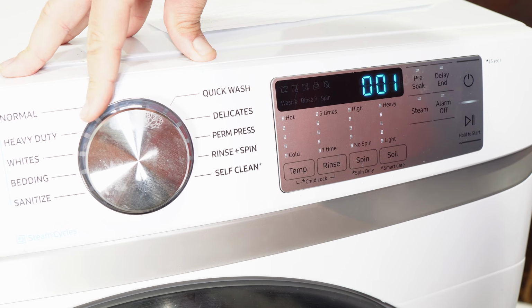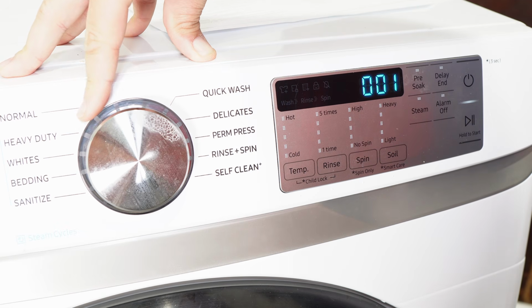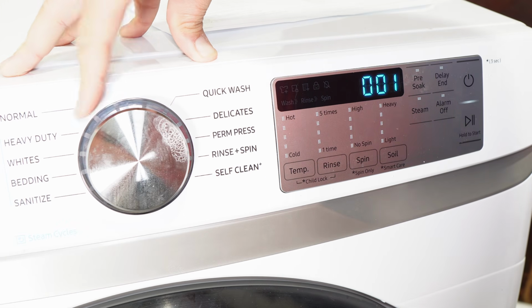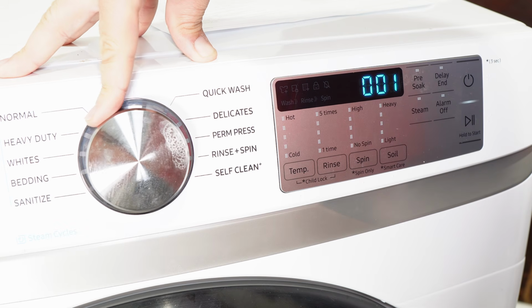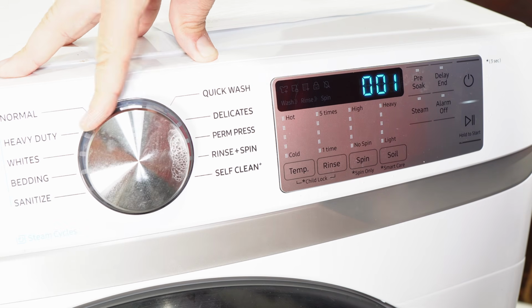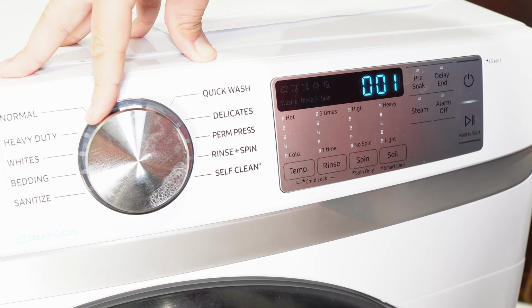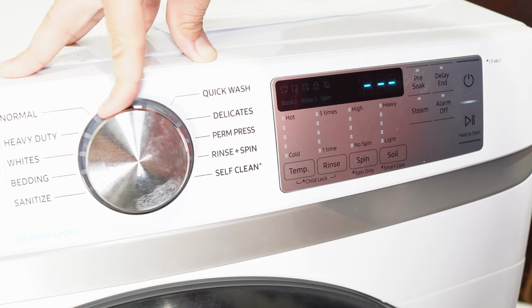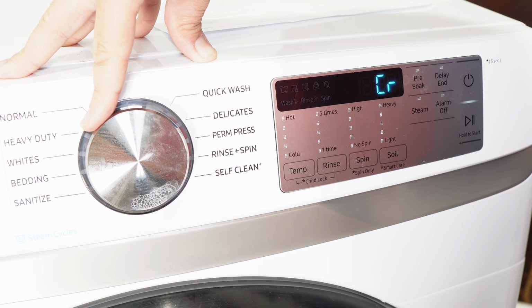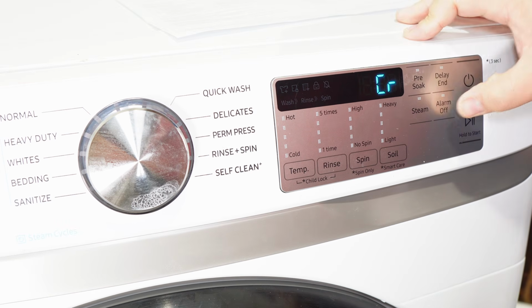So you will have to scroll through using the jog dial until it gets back to the CR lettering, and then it will start at the beginning with the error codes. I have the UE unbalanced code in the case of this unit. If you go through and you do not have errors, you will get the 3 horizontal lines each time you turn the dial. When you are done with this, you are going to have to press the power button to turn the unit off, and then you can turn it back on for whatever use you have.